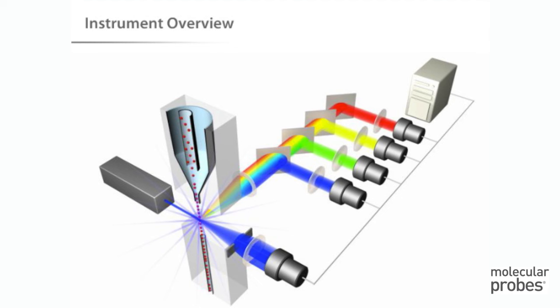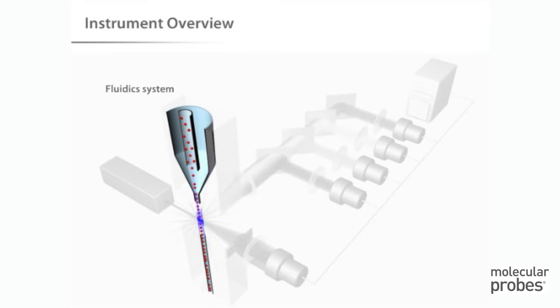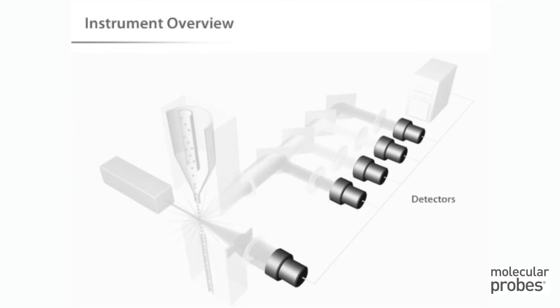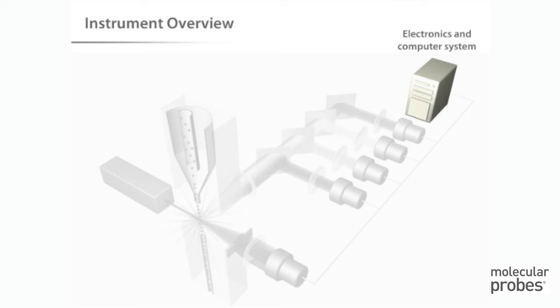This view shows the primary systems of the flow cytometer schematically. These are the fluidic system, which presents samples to the interrogation point and takes away the waste, the lasers, which are the light source for scatter and fluorescence, the optics, which gather and direct the light, the detectors, which receive the light, and the electronics and the peripheral computer system, which convert the signals from the detectors into digital data and perform the necessary analyses.